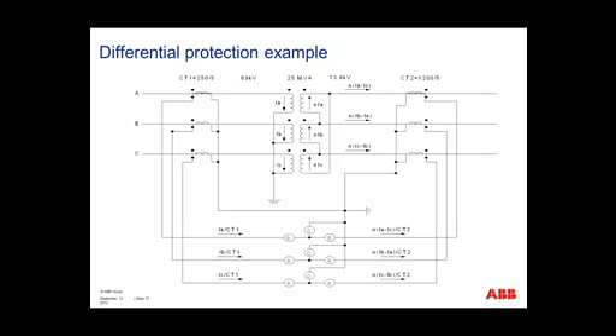However, if you look at the connections of the CTs themselves, our measuring current transformers, we have a Y-connected CT on the high side and a Y-connected CT on the low side. So if we take, for instance, A phase, the current coming in the CT is proportional to IA divided by the CT ratio. On the low side, because of the delta connection, the current coming in is A minus C divided by the CT ratio. If this was hooked up, the currents would not be balanced between the high and low side. We'd have current passing through our operate coil, and we would have a misoperation.